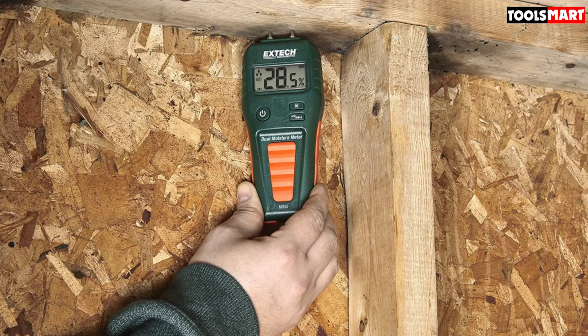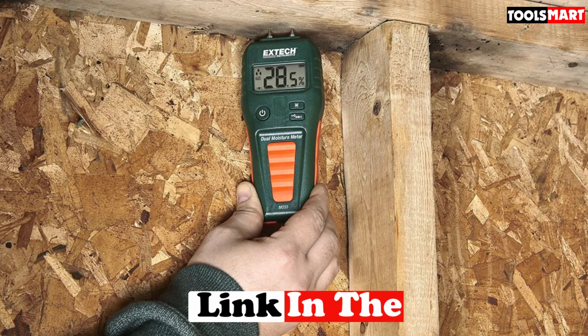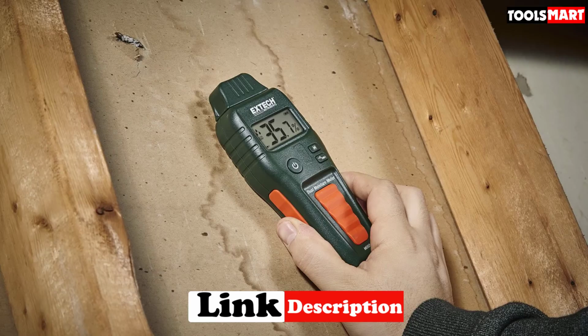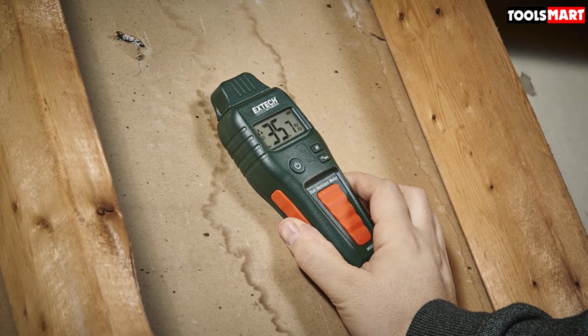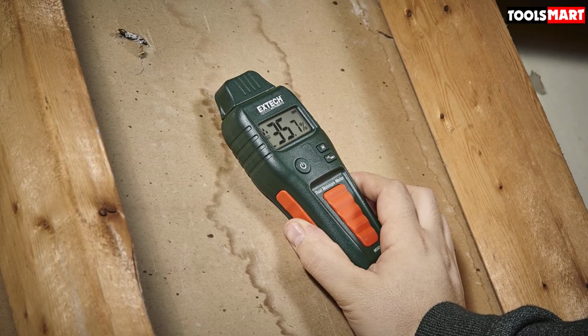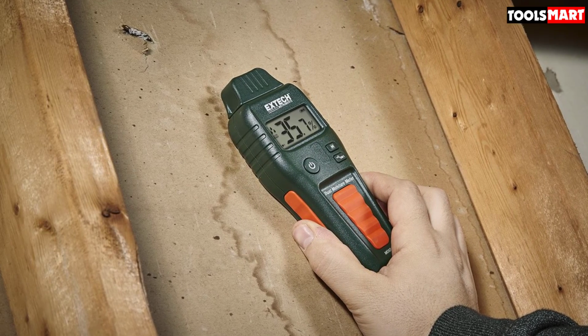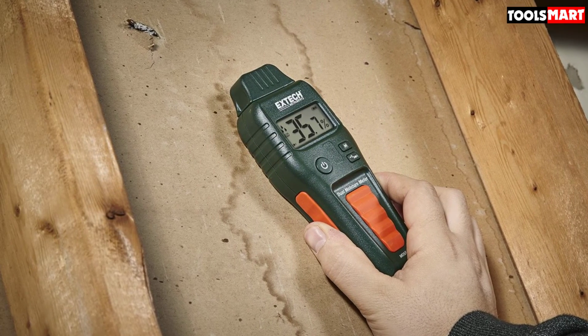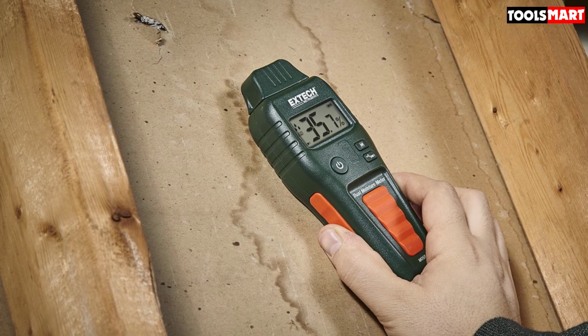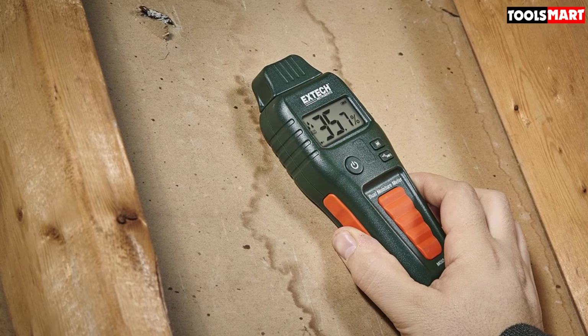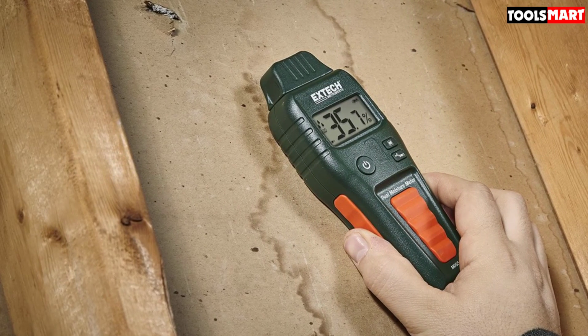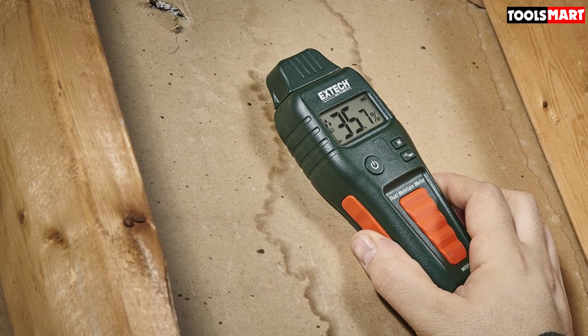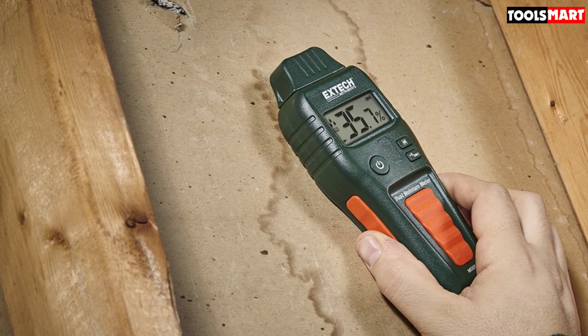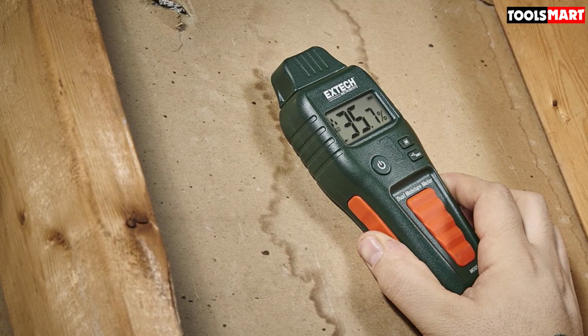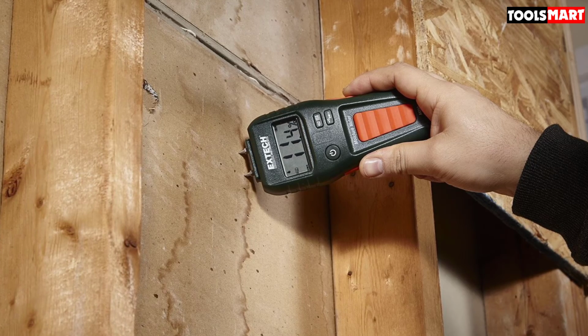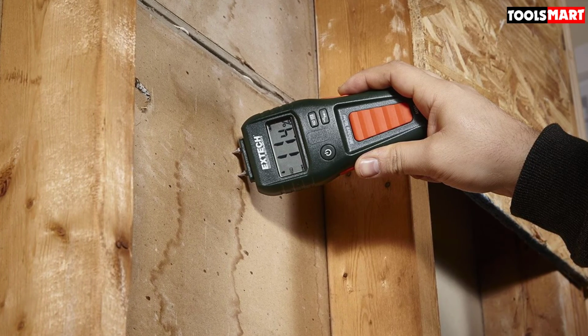You can use this device for measuring the moisture content in concrete, mortar, wallboard, and cardboard. It also measures low, medium, and high levels of moisture, adding to its versatility. We wanted a moisture meter that would detect moisture content in a wide range of wood and building materials, and with this device, we could detect moisture content from low to higher levels across any measurement range.